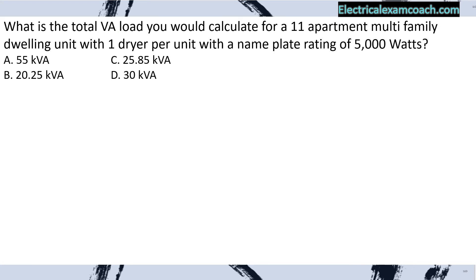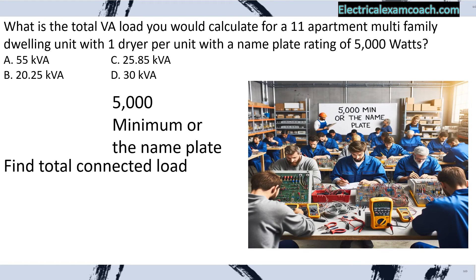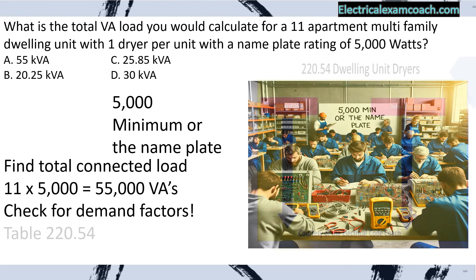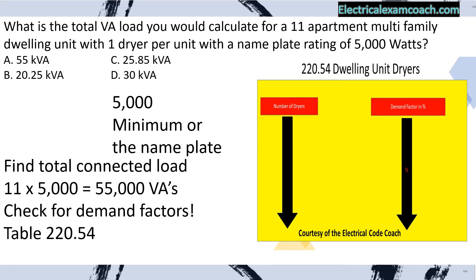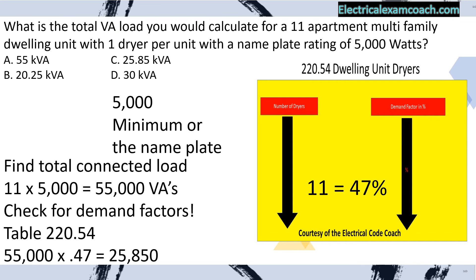What is the total VA load for an 11-apartment multifamily dwelling with one dryer per unit and a nameplate rating of 5,000 watts? We find our total connected load: 11 units multiplied by 5,000 equals 55,000 VAs. We then check table 220.54 and find the demand factor for 11 dryers is 47%. We take our original load multiplied by 0.47, giving us a new reduced load of 25,850 VAs. Answer: C.